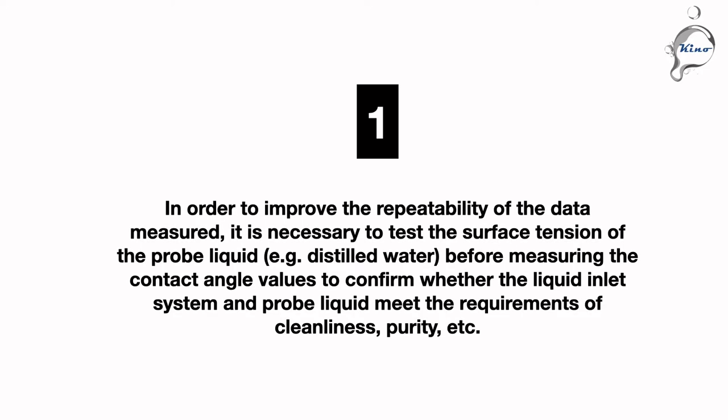In order to improve the repeatability of the data measured, it is necessary to test the surface tension of the probe liquid, such as distilled water, before measuring the contact angle values to confirm whether the liquid inlet system and probe liquid meet the requirements of cleanliness, purity, etc.